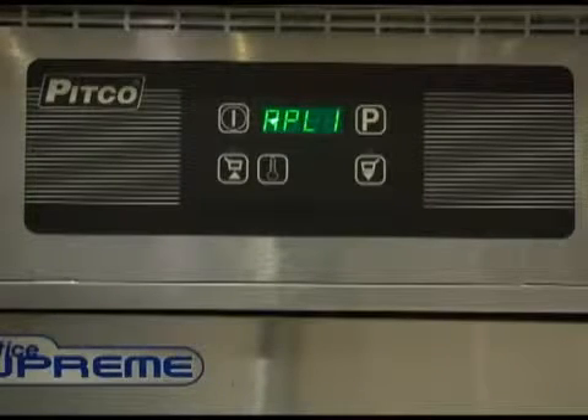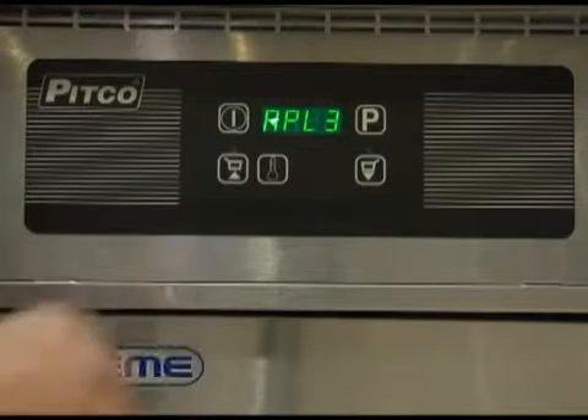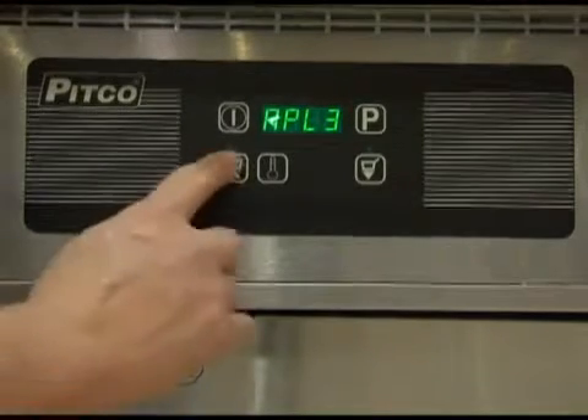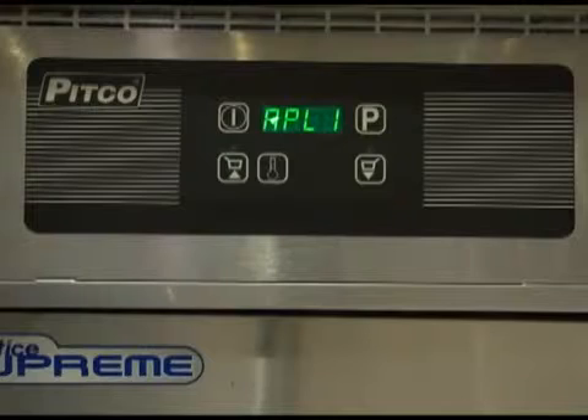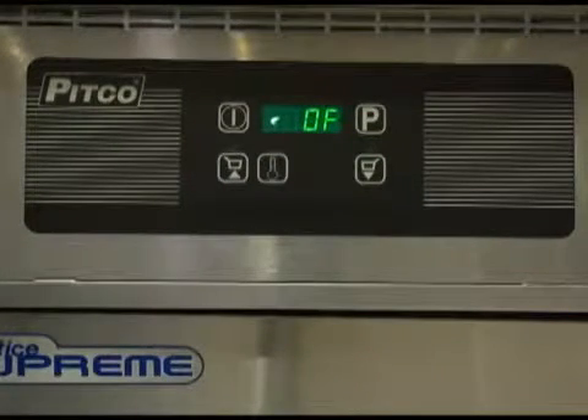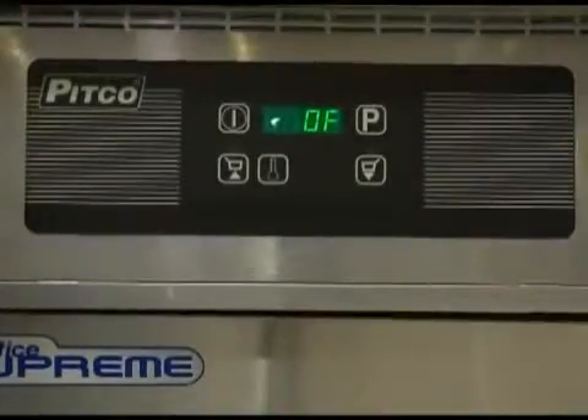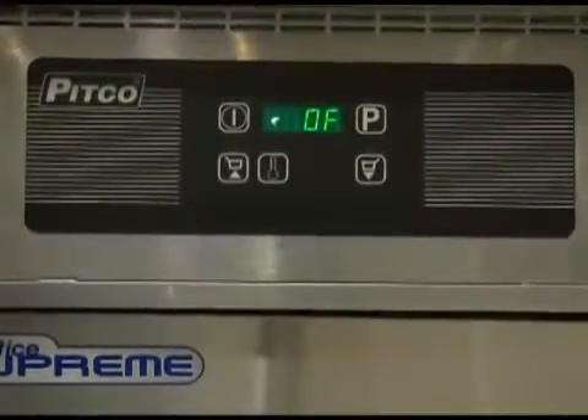The display should now show the current appliance type the controller is set for. APL1 is selected for gas appliances, APL2 is selected for electric appliances, and APL3 is for a general thermostatically controlled appliance. Once set correctly for the appliance type of your equipment, press the program key to save and move on to the next option. The display should now show an option for a control point offset.